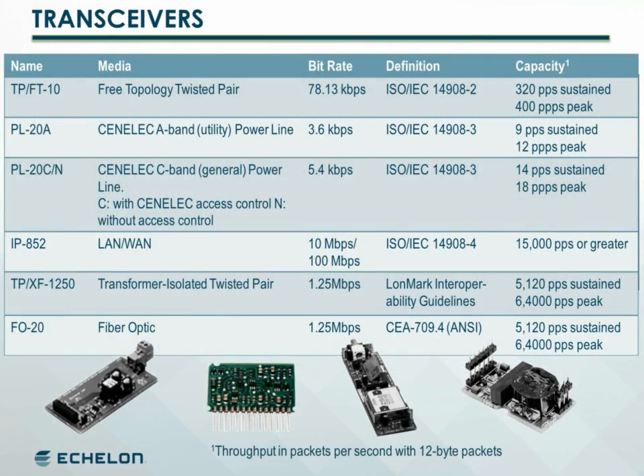Each LonWorks device has a transceiver which matches the appropriate transfer media or communications channel. The chart lists some common LonWorks communication channel types. Transceivers simplify the development of interoperable LonWorks devices and are available for a variety of communications media and topologies, with the most common types being free topology twisted pair and power line.